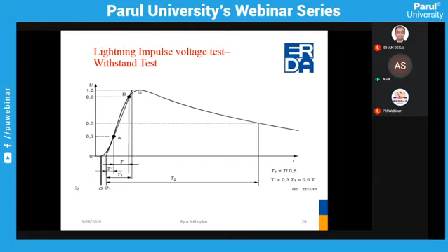The wave shape should be 1.2 by 50 microsecond. But you know that in the laboratory the exact 1.2 by 50 microsecond may not always be possible. So tolerance is given: in the test voltage plus minus 3%, in the front time plus minus 30%, and in T2, that is the tail time, plus minus 20%.